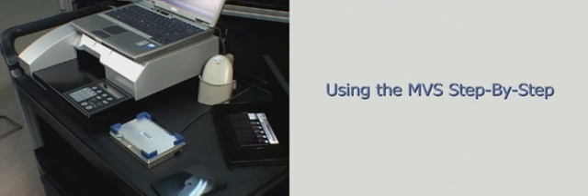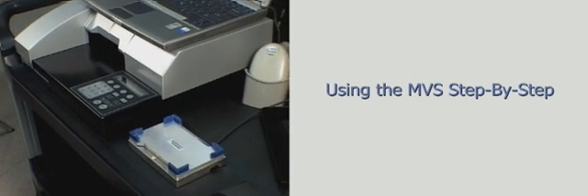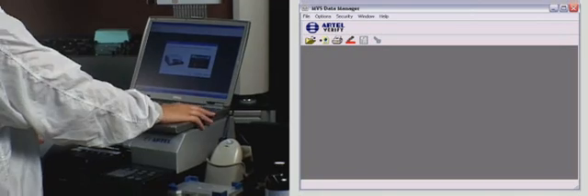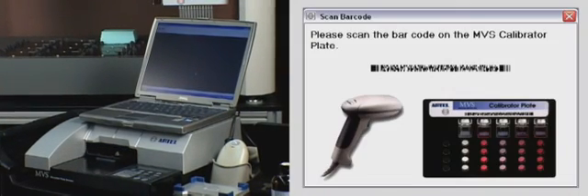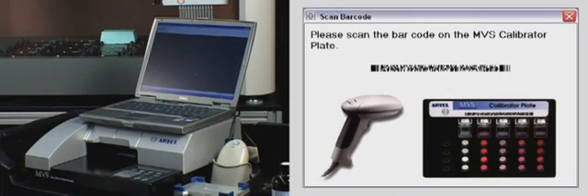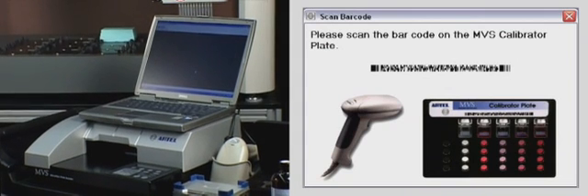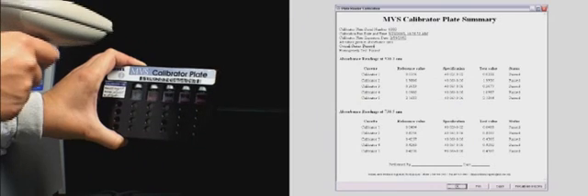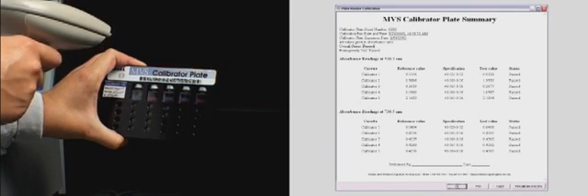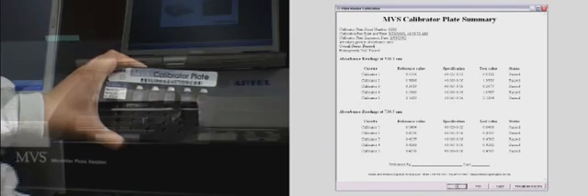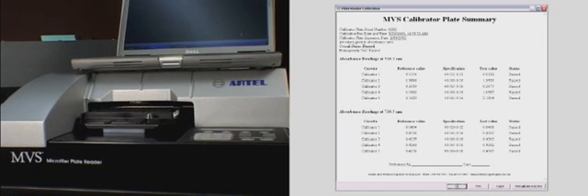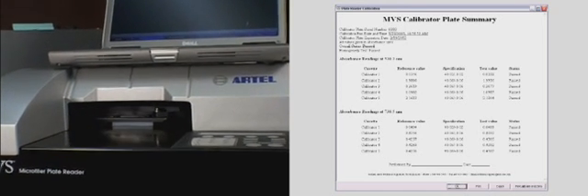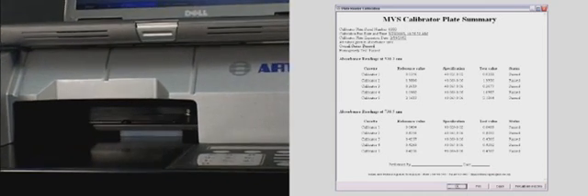Let's now review the procedural steps and performance of the MVS. Start the system using the MVS icon on the desktop. The software provides for 21 CFR Part 11 compliance. Using the calibrator plate, extend traceability to the plate reader by calibrating at the beginning of each day. The plate is scanned with the barcode reader. In less than one minute, the plate reader will be calibrated. The calibrator plate ensures the plate reader is normalized to the NIST traceable standards and provides accurate and repeatable MVS results.